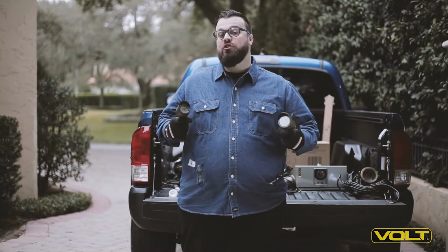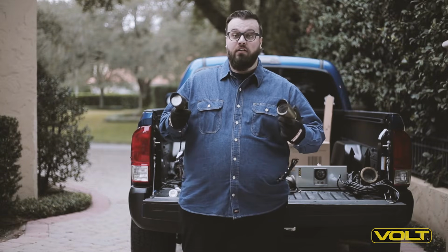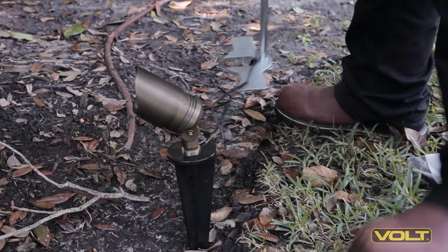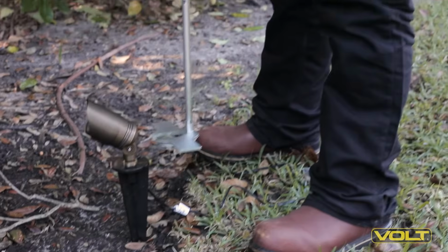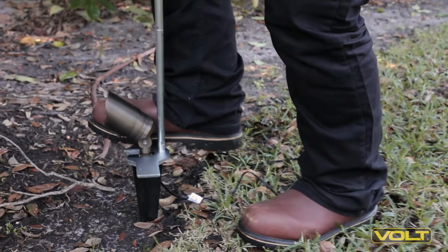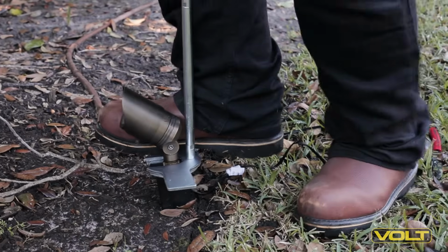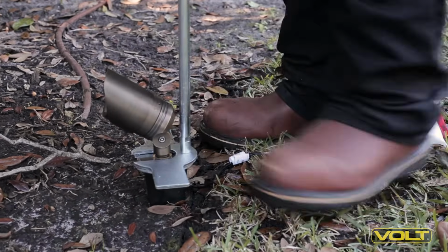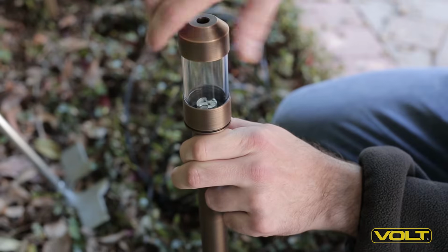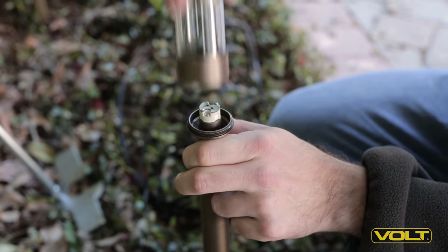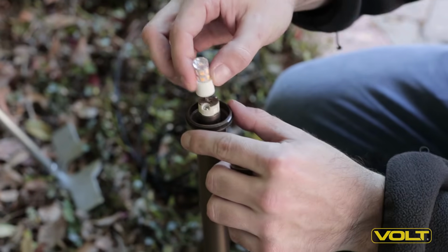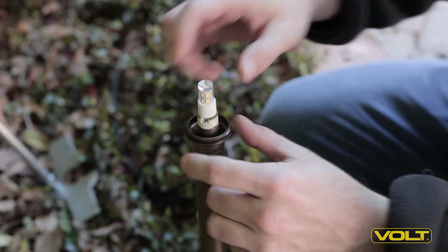There are two main fixture classes. You've got integrated and lamp ready. Integrated fixtures have an LED board built into them, which speeds up installation because there's no bulb to install. The downside to integrated fixtures is that because they are integrated, if one should fail, then the entire fixture has to be replaced as opposed to just a bulb. Retrofit fixtures take a bulb, which allows for much more customization within your lightscape, but they require the extra step of choosing and installing a bulb for each fixture.